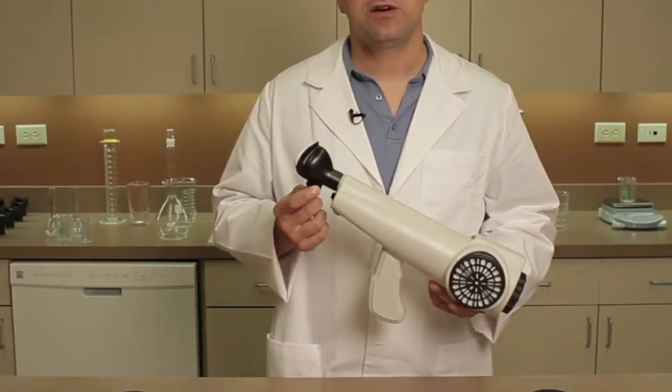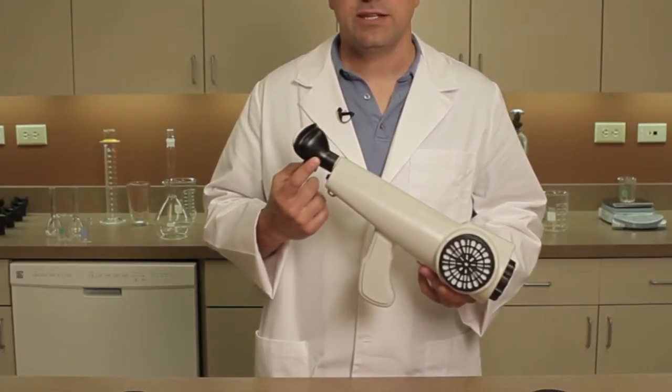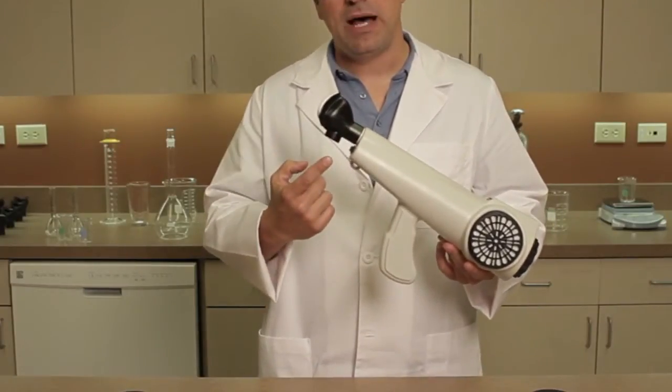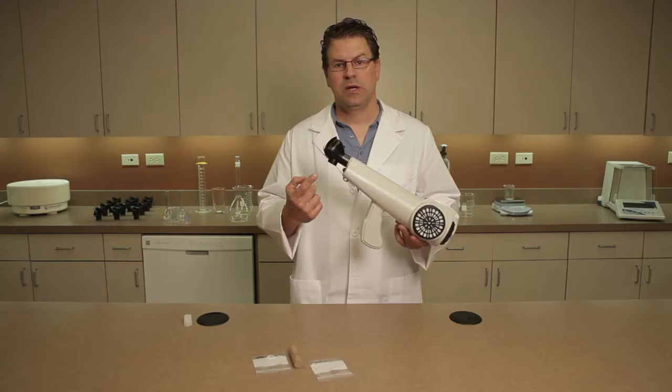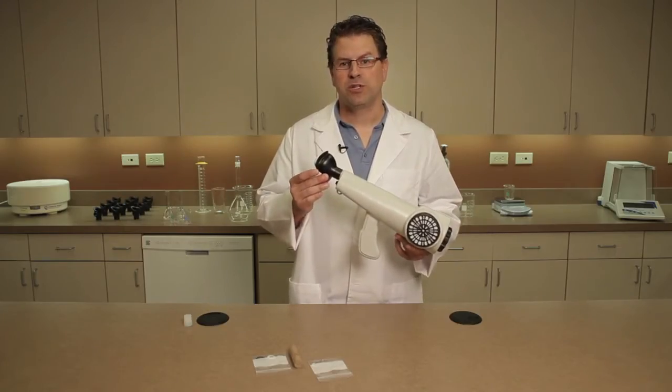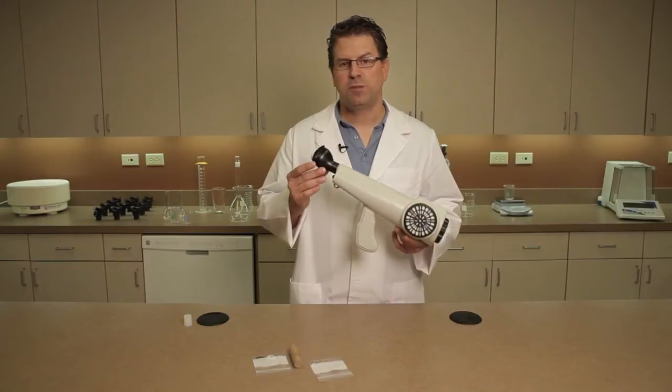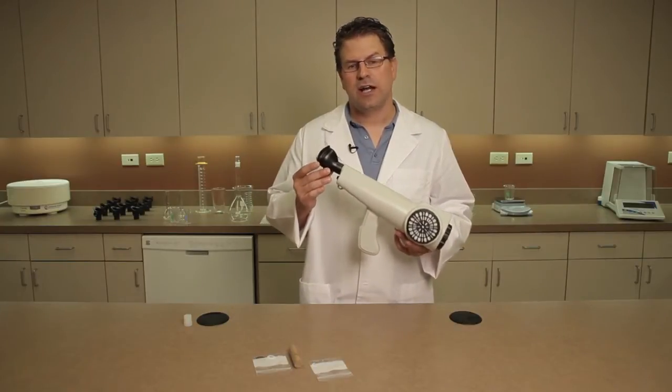The user sniffs the odorous air through the Nasal Ranger and into the mask and then exhales out the bottom away from the user. These check valves should be inspected for proper operation before each use and changed periodically, so let's take a look at how that's done.